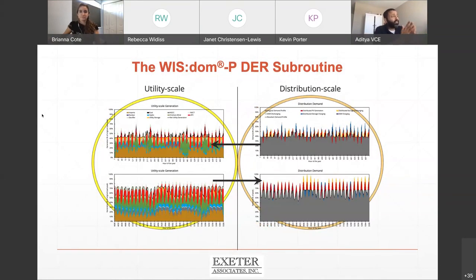Here's a quick example of that in work. What we see on the left side is the full dispatch, whereas on the right side, the two panels show in gray the portion of the dispatch coming from the utility scale generation. When the distribution co-optimization is turned off, in the top two panels, we see the utility scale generation has to ramp up and down to ensure it meets load, which is a little non-optimal in terms of operation. In the bottom two panels, with the co-optimization turned on, the distributed resources shift load to ensure a smoother load as seen by the utility scale generation, which increases the load factor and results in more effective operation of the utility grid and reduces costs. That's an example of what the DER co-optimization can help with.